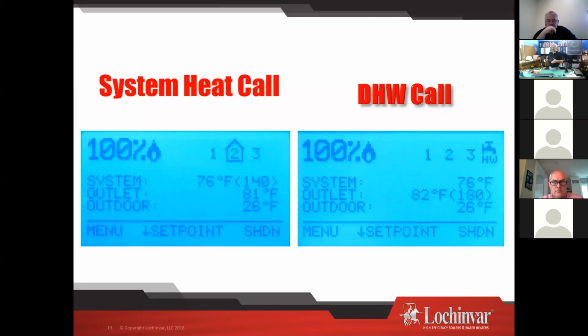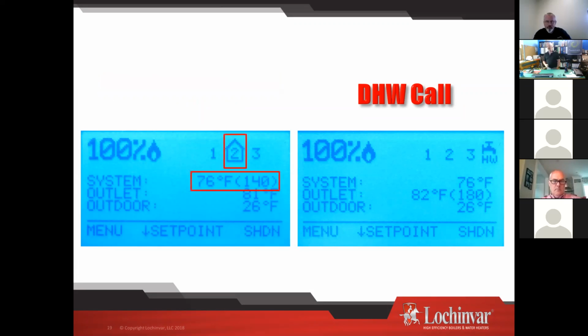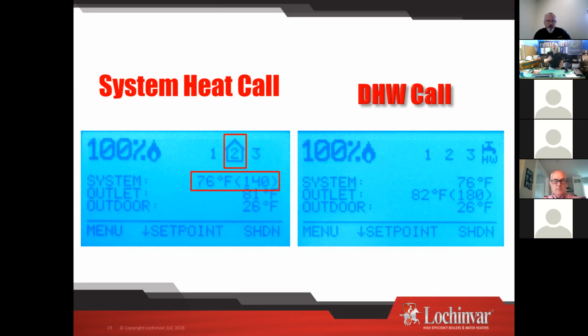All right. What happens when I get a call for heat? This is what we're going to look at here. What does this display tell us as we look at it? Left-hand side, I'm showing a system heat call. Right-hand side, a domestic hot water call. How can you tell the difference? Well, the 2 is lit up with the house on it. What does the house mean? Well, we had 3 different temperature demands. So right now it's showing you that all 3 temperature demands are calling, 1, 2, and 3. It's telling you by putting that house over number 2 that number 2 is calling for the warmest water right now. So it has basically priority.